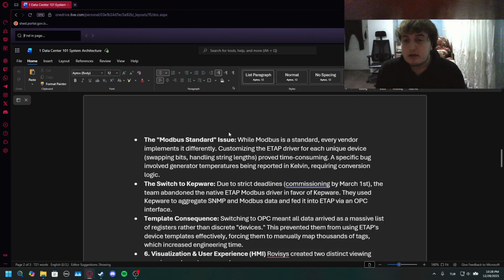Template consequences: switching to OPC meant all data arrived as a massive list of registers rather than discrete devices. This prevented them from using ETAP's device templates effectively, forcing them to manually map thousands of tags, which increased engineering time. You thought you would get to the deadline faster, but in this case, they might not have.